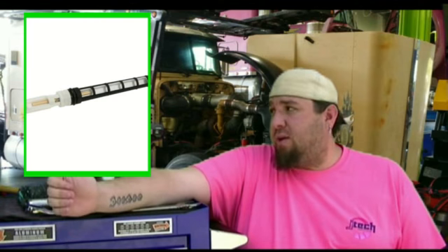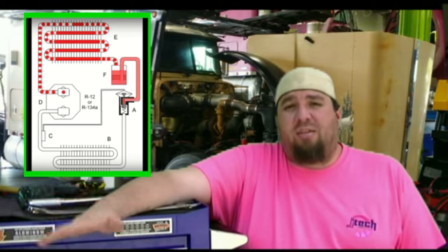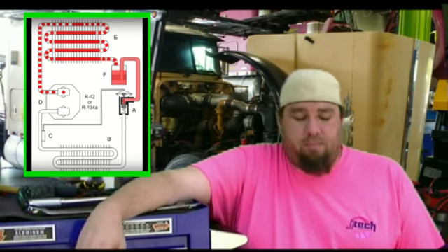Now from there, the refrigerant, once picked up by the tube, is going through. You're still dealing with a high pressure subcooled liquid. So it'll go into the next component, which will be your valve. That will either be an orifice tube, as pictured here, or this will be an H-block style valve, or a TXV, thermal expansion valve. Now, as I said, it's coming in as a high pressure subcooled liquid.